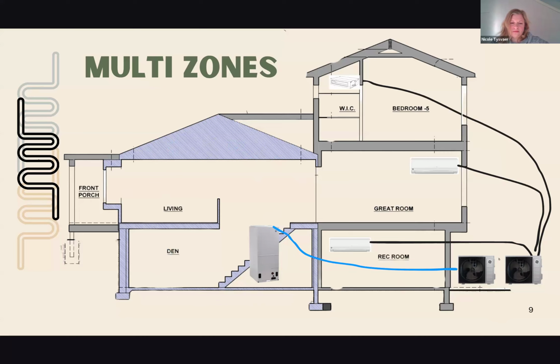We used our heat pump air handler there and connected it to our existing duct, which we modified because the ductwork was decades old and the setup was not how modern technology tells us to do it. And by modified, he means we tore it all out and redid it. But we did keep the bulkhead in the basement. So that's how we addressed that.